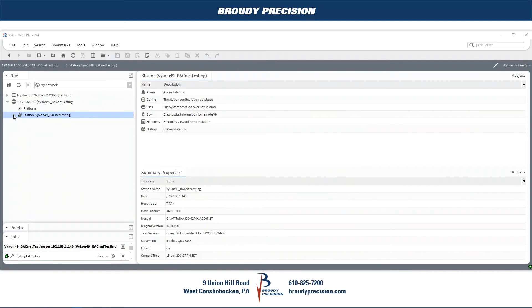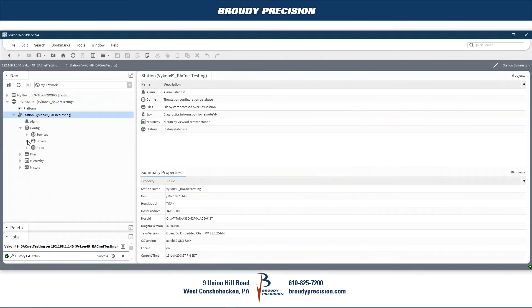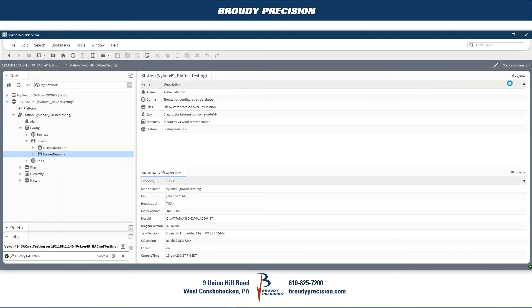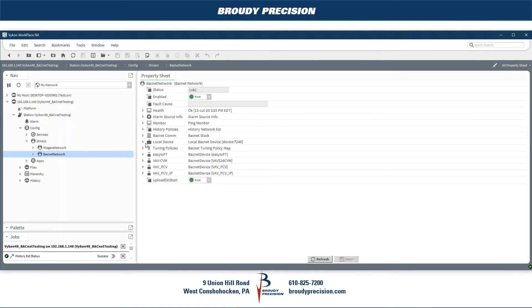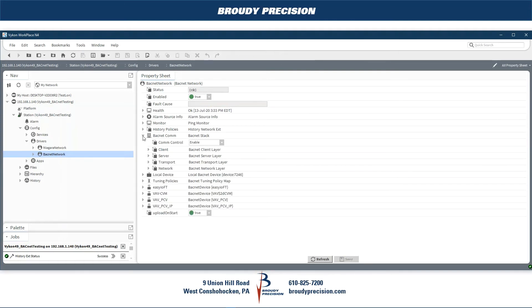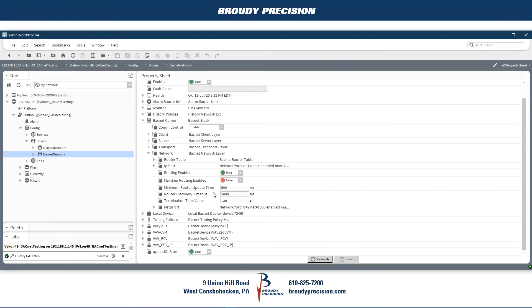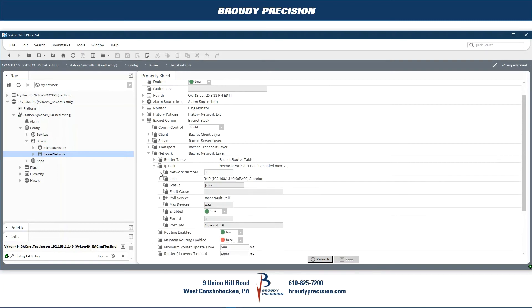Now I'll show you in Niagara what to look for, and then we'll go into CCT as well. In the Workbench, we'll go down to our BACnet network, go to the property sheet, and check the settings so we know what we need to do within CCT. Going underneath our BACnet network, we go to BACnet COM, then our network. Under there you'll find the IP port and the routing enabled setting — make sure that's set to true so you can use the JACE as a router.